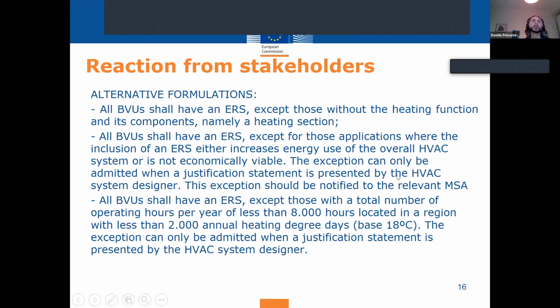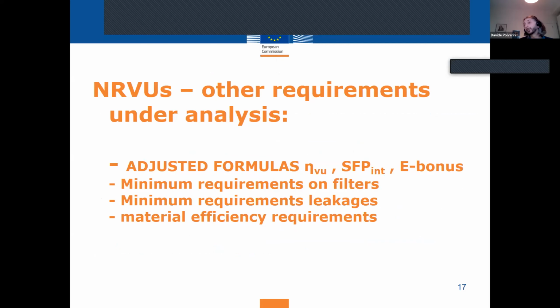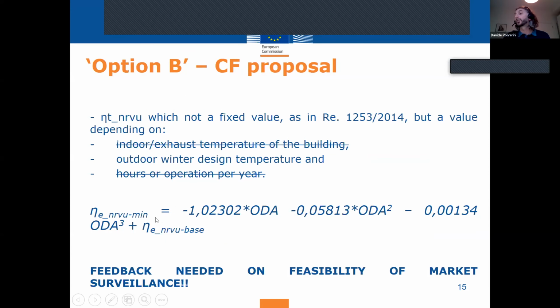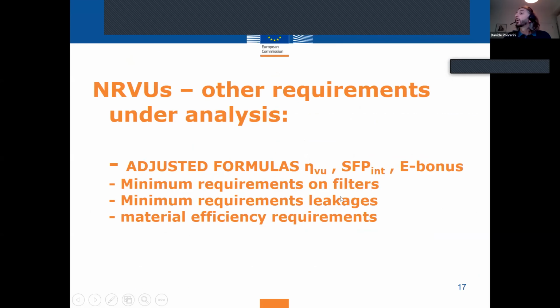So just to mention that for this requirement, as for the others we are evaluating, because we are only talking about one of the requirements under review, we've received a lot of feedback, and we are now in the process of elaborating, of reasoning, of understanding what of all this feedback can be taken into account and what can remain as per the original proposal. I don't have time to go into the detail, but please consider that we are also considering for the review of the regulation a lot of other modifications. So adjusting these formulas, for example, for the internal specific fan pressure, which would be as well, as you could see for the heat recovery efficiency, would become dependent on the geographical location.